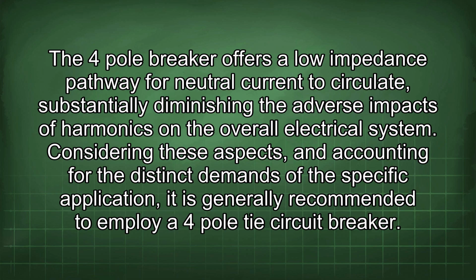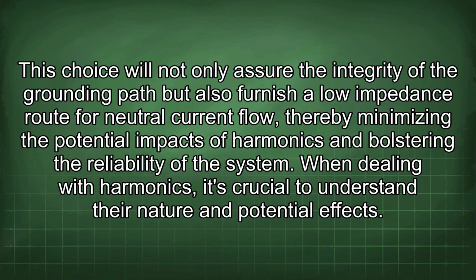Considering these aspects, and accounting for the distinct demands of the specific application, it is generally recommended to employ a 4-pole tie circuit breaker. This choice will not only assure the integrity of the grounding path, but also furnish a low impedance route for neutral current flow, thereby minimizing the potential impacts of harmonics and bolstering the reliability of the system. When dealing with harmonics, it's crucial to understand their nature and potential effects.